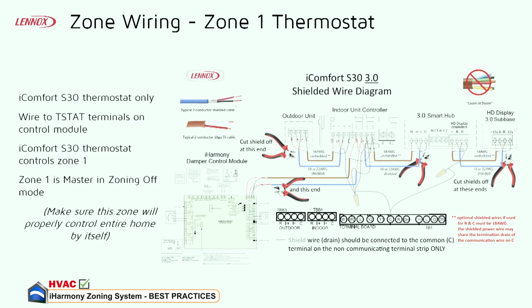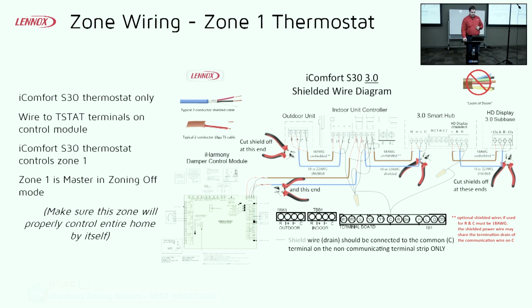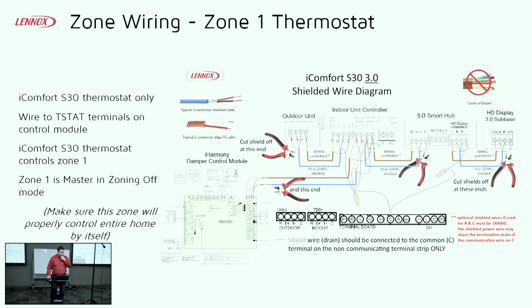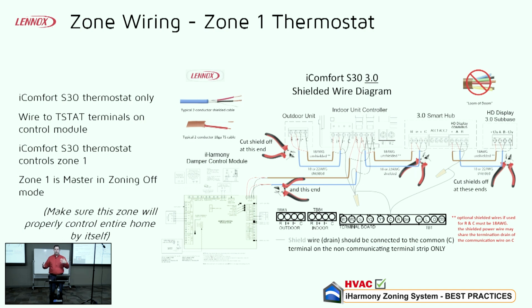A lot of times the most critical point here is going to be this connection at your indoor unit. Because you'll notice what they have here is the wiring from your smart hub and the wiring from your zone board piggybacked onto those indoor terminals. That's your furnace or your air handler. That seems to be the most critical component there, where the hub's talking to the furnace and the zone board's talking to the furnace.